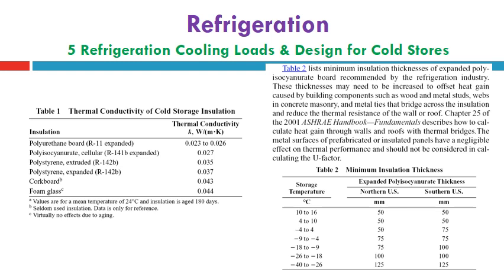based on the different materials listed in this table, which is commonly used for the wall material as an insulation with very low thermal conductivity to reduce the transmission heat load from outside to inside. However, on the right side of this slide we can find Table 2. Table 2 lists minimum insulation thickness of expanded polystyrene, polyisocyanurate boards recommended by the refrigeration industry.